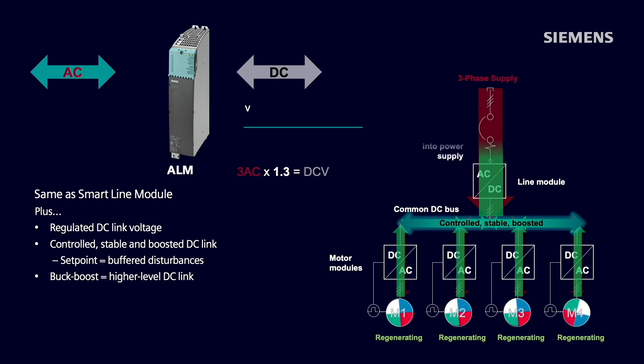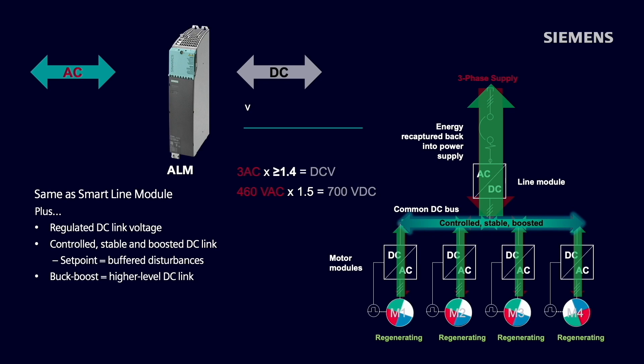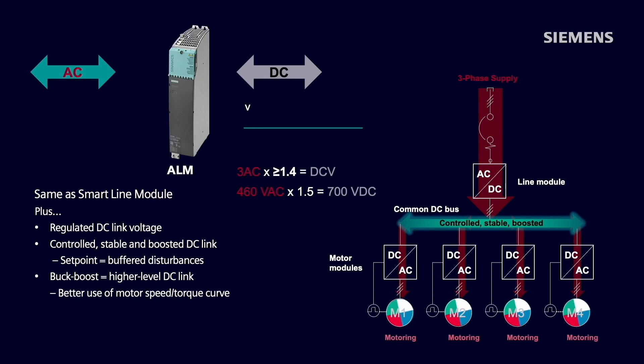The DC link is also a buck boost, so the DC link level will be higher with an active line module. Typically, we would be in the 1.3 range for the basic line module and smart line module, but an active module starts out at a 1.4 factor range. Typical default would be a 1.5 factor on the book-sized drive system, but could be regulated up to twice the incoming three-phase AC voltage. At a default value of about 1.5, at 460 volt supply, we would have a regulated 700 volt DC bus. This higher voltage allows us to better utilize the motor speed torque curve.